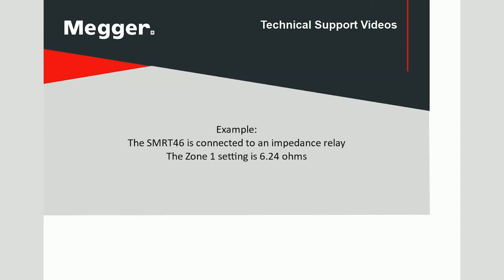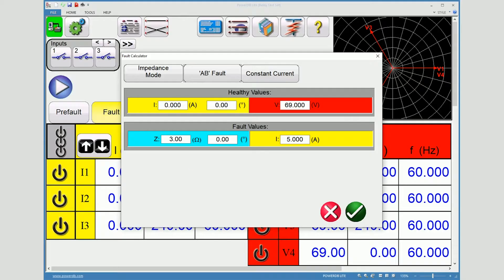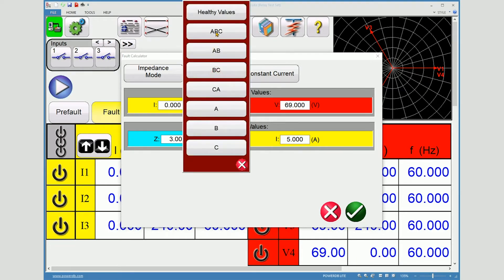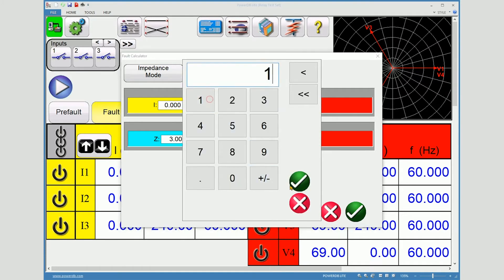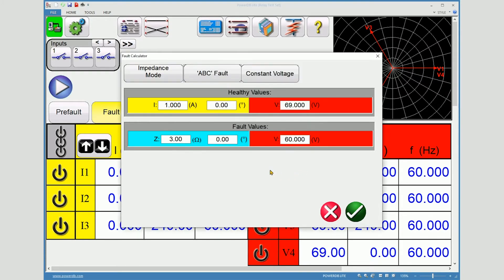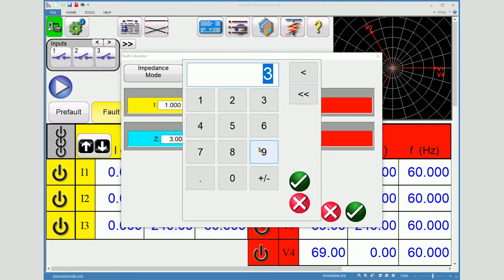For this example, the SMRT46 is connected to an impedance relay. The zone 1 setting is 6.24 ohms. I will perform a manual pickup test. Using the fault calculator, I will set a three-phase fault using constant voltage. Pre-fault healthy current will be 1 amp. The setting is 6.24 ohms, so I will set something slightly larger than that.